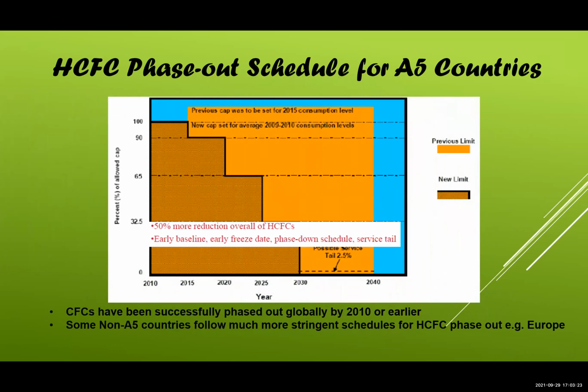Yeah, so in most of the developing countries, we still use HCFCs because HCFC can be used up to 2030. For instance, in a country like India, we are still using HCFC 22, R22, in the air conditioners, but new R22 equipment is not sold. It has been banned, and most of them will use R410A, R32, R290. But R22 is still used in service, and by 2030 you have to stop using R22 or R123. So this is the phase out. We have gone through this, and only a small portion is allowed for tail. But I can tell you, the market is moving faster than these regulatory steps. That's where the environment gets saved.